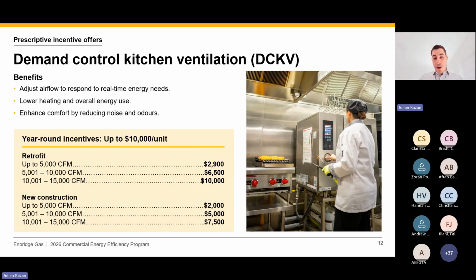Here's another popular one that we incentivize: demand-controlled kitchen ventilation. For those with commercial kitchens, staff often flip on the exhaust in the morning and leave it running all day, then maybe turn it off when they leave, or maybe not at all. Demand-controlled kitchen ventilation alleviates that problem. It measures the temperature above the grill, looks for particulate matter like smoke above the grill, and modulates your exhaust based on the activity of the cooking.